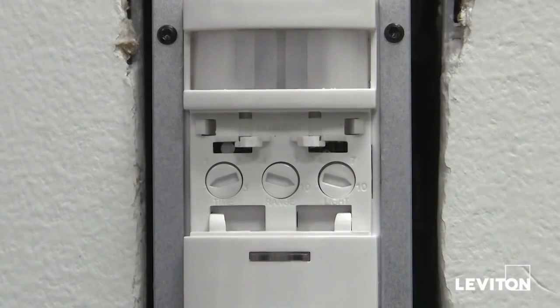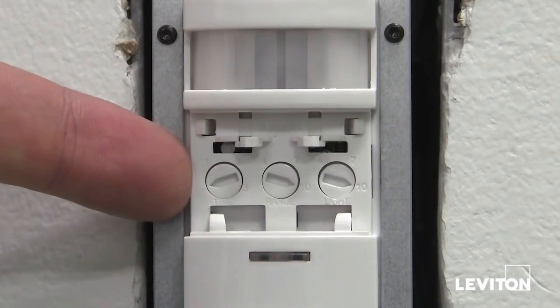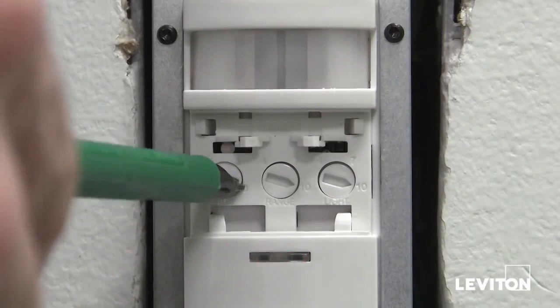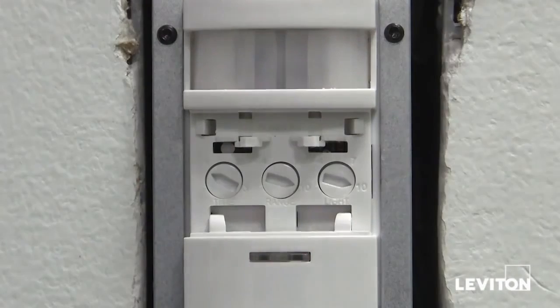The slash mark located all the way clockwise is a 30-second timeout used for the walkthrough test. It can also be left at that selection if you have a 30-second timeout desired. One is a 10-minute timeout, two is a 20-minute timeout, and three is a 30-minute timeout.